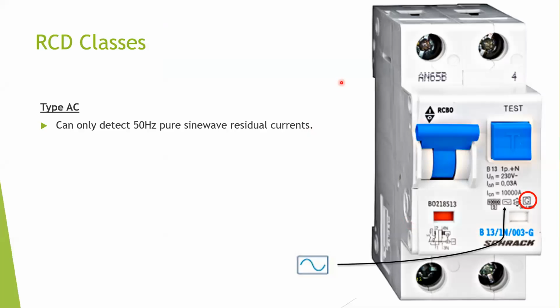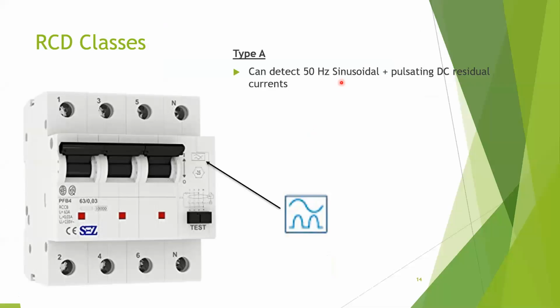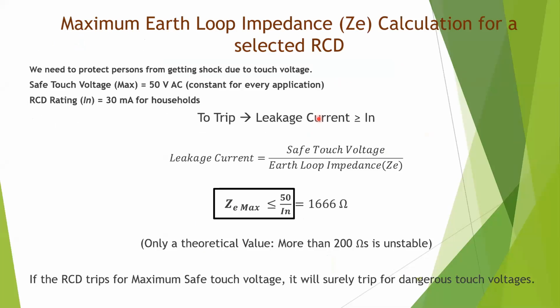Okay, so now we discussed RCDs. I said these RCDs have ratings, right? In Sri Lanka, the most common one is 30 milliampere. So we need to do our earthing arrangement design and earth loop impedance design according to this RCD rating. We discussed that safe touch voltage is 50 volts AC, constant for each application. You should remember this value, very important. Safe touch voltage is 50 volts AC.